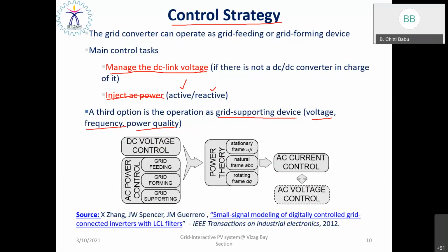So sometimes the grid may not be available. When the grid is under fault, the PV can still feed power to the local load. Now the load is said to be under isolated or off-grid condition, right? So the option may be included for control during microgrid conditions as well. As it has to handle the input parameter of the inverter, which is DC voltage control, and the output power from the inverter is basically AC, it has to have AC current control as well as AC voltage control. And moreover, as the grid is AC in nature, there is the control option on the AC power in terms of grid feeding, grid forming, or grid supporting, irrespective of the grid conditions.